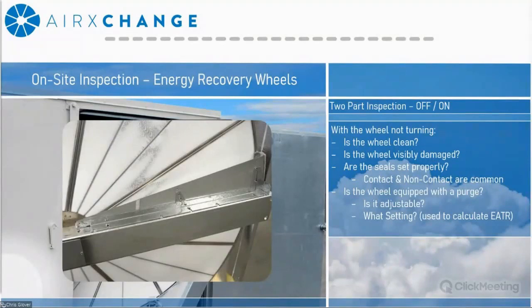I'd like at this point to say that not all systems are equipped with a purge, and really not all systems require a purge. Once again, certain carryovers are acceptable by the ventilation standard. So if you're within the ventilation standard procedure, you sometimes don't need these. But you're going to want to take note if your system does have one of these, and whether it's adjustable or a fixed plate, as these settings are going to help determine what the potential recirculation is, or what the EATR is going to be, when you do the analysis.